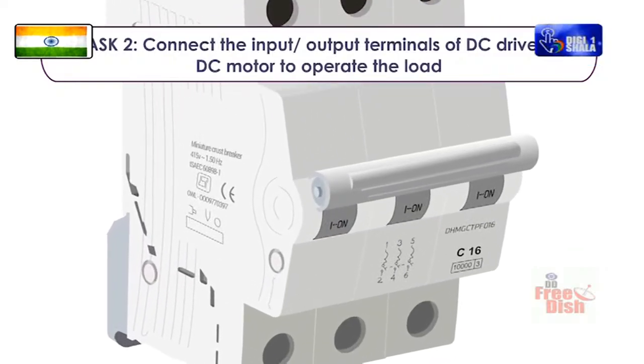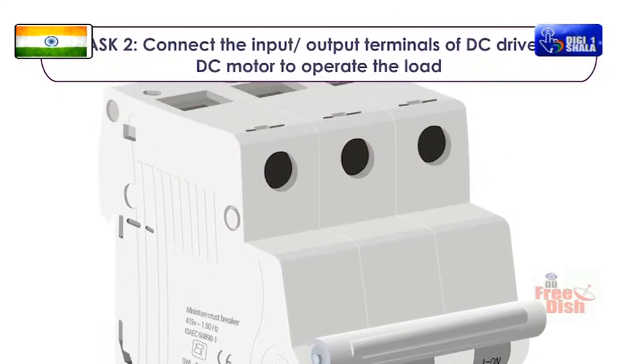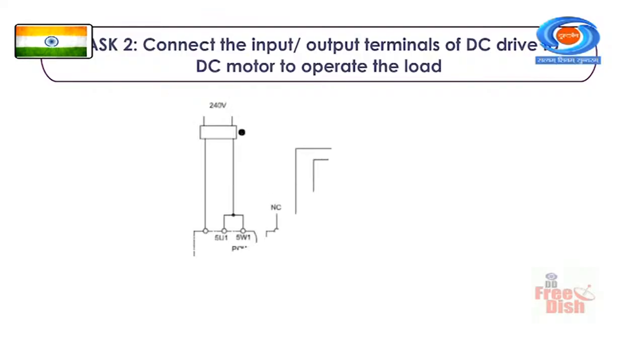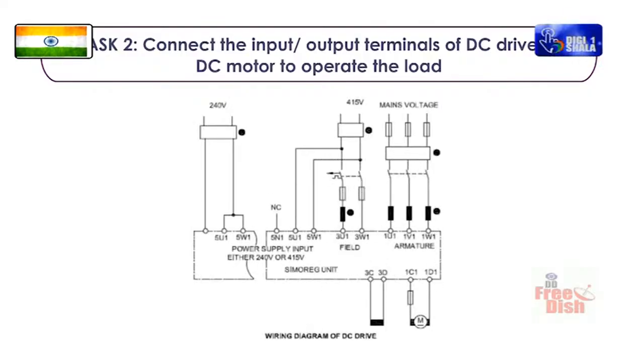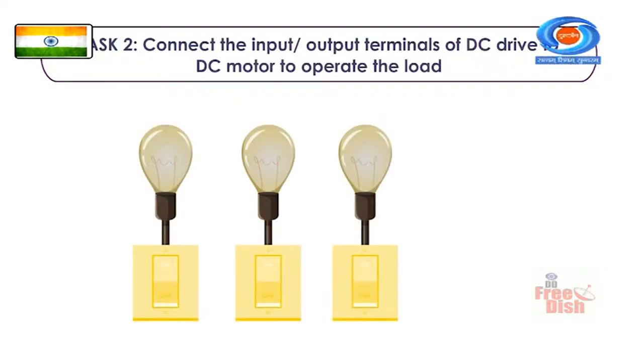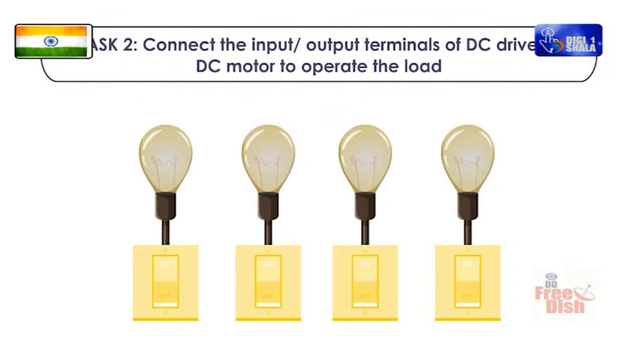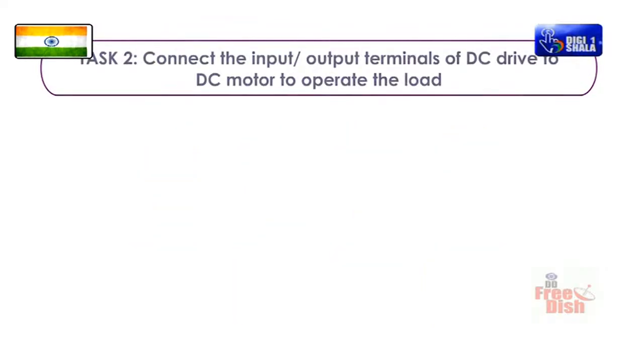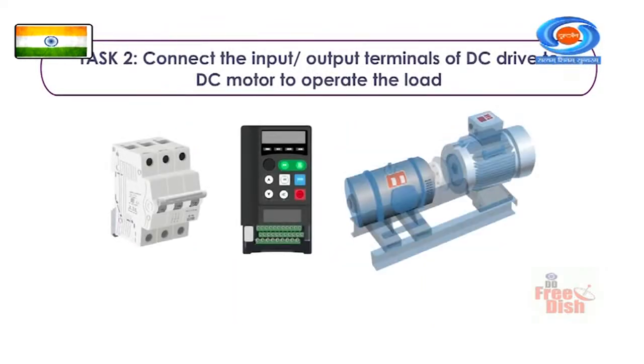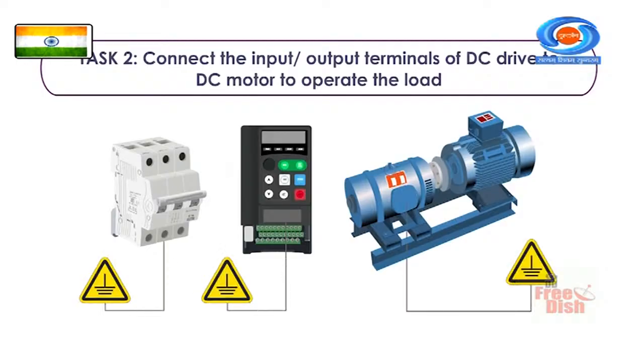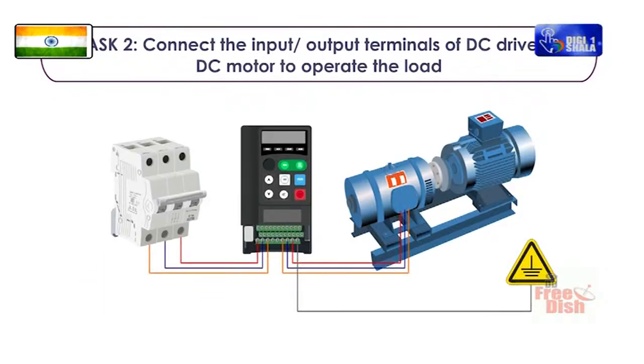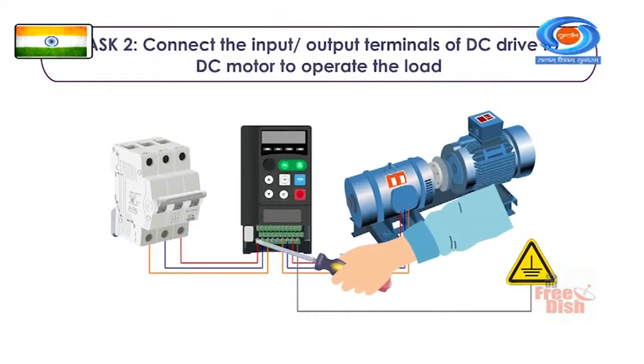Select the ICTP switch or MCB, cables and fuse wire according to the rating of the motor. Draw the circuit diagram and connect the ICTP, MCB, drive and the motor as shown. Connect with the main switch or MCB four 500 watt clear lamps fitted in an enclosure, having individual on-off facility. Connect double earth independently for the main switch, DC drive and the motor. Check the supply and ensure proper rating of the fuse and main switch according to the motor rating.